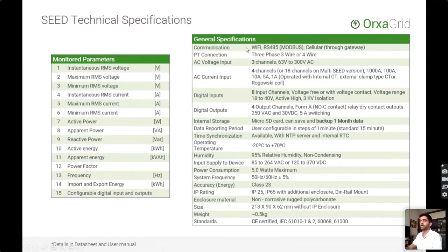In terms of communication, like I mentioned, it comes with Wi-Fi and RS485. And then to push it to the cloud, we use cellular through a gateway. PT connections are three-phase, four-wire. That is the standard, but you also get three-phase, three-wire communication for Delta connections. Per phase calculations of voltages, per phase calculation of current, and we do clamp-on CTs, so there is no burden on the existing connections. So you can use either clamp-on CTs or Rogowski coils for flexible installations, especially handy in distribution market where there are non-standard cable lengths or cable diameters in place.